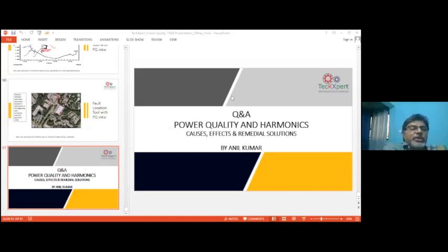The first question I saw was: how to evaluate the source of harmonics. It's a very good question. It's a very tricky subject, finding the source of harmonics, because there is a phase angle between voltage and current at the fundamental frequency, and also a phase angle between voltage and current at higher frequencies. For example, if you take a fifth harmonic current or a fifth harmonic voltage, there is a phase angle difference there also. Phase angle is used to compute the power flow.